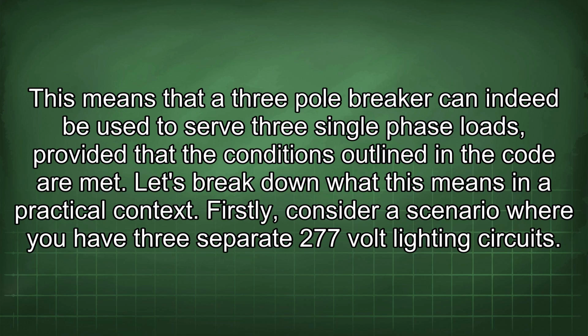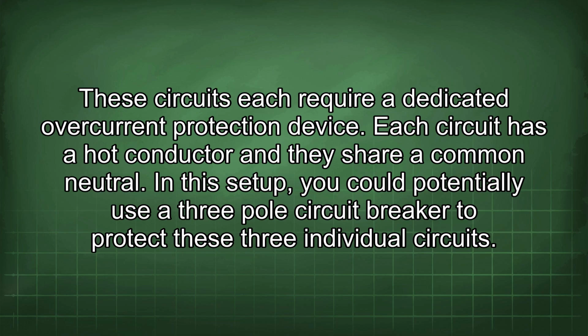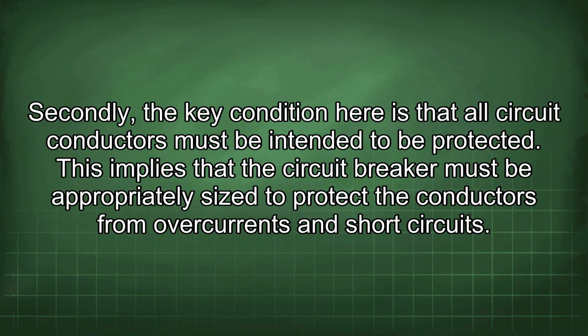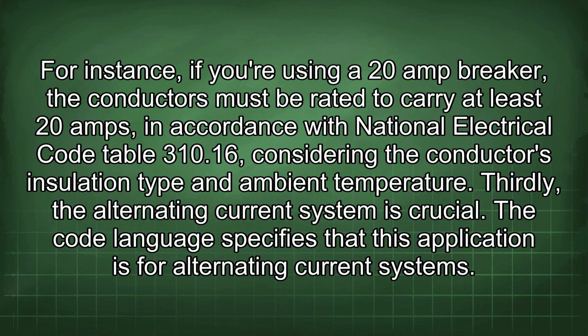Firstly, consider a scenario where you have three separate 277-volt lighting circuits. These circuits each require a dedicated overcurrent protection device. Each circuit has a hot conductor and they share a common neutral. In this setup, you could potentially use a three-pole circuit breaker to protect these three individual circuits. Secondly, the key condition here is that all circuit conductors must be intended to be protected. This implies that the circuit breaker must be appropriately sized to protect the conductors from overcurrents and short circuits. For instance, if you're using a 20-amp breaker, the conductors must be rated to carry at least 20 amps, in accordance with National Electrical Code Table 310.16, considering the conductor's insulation type and ambient temperature.